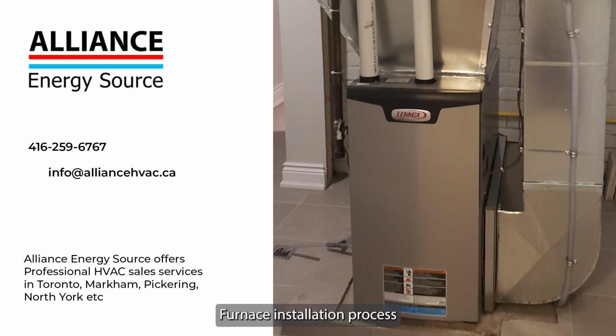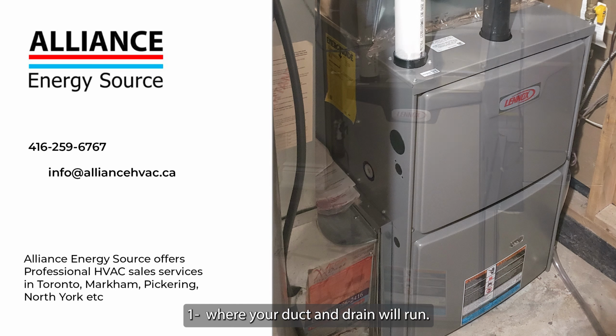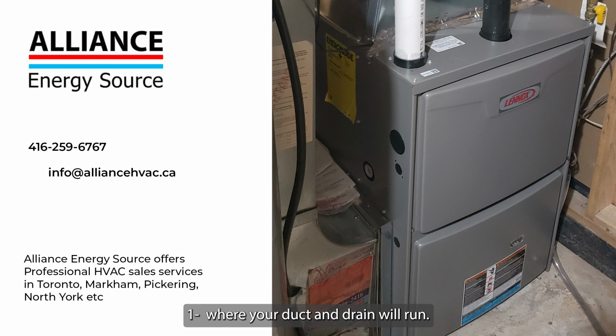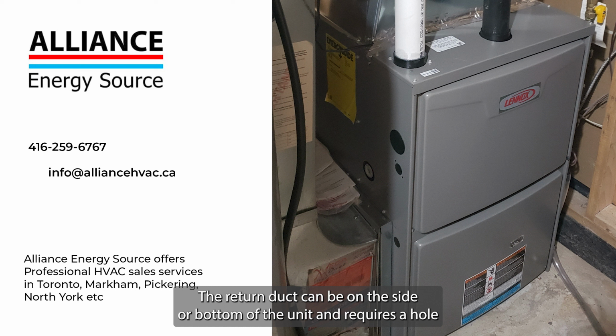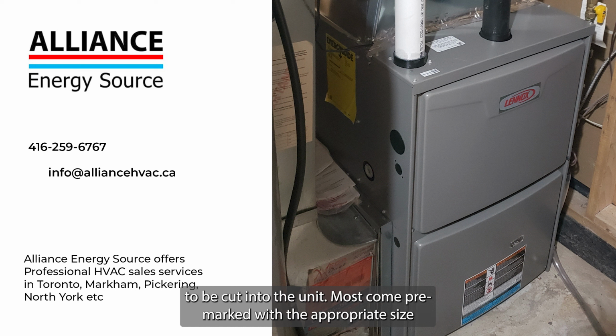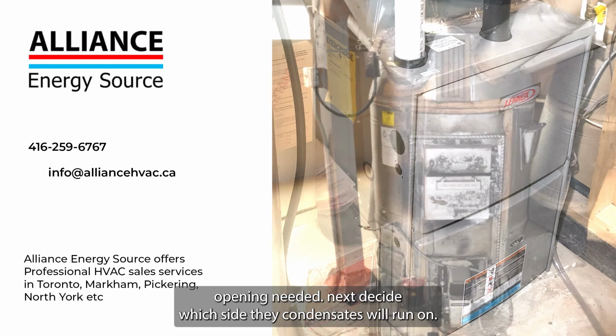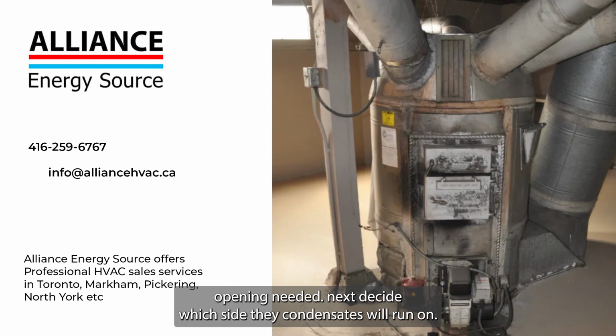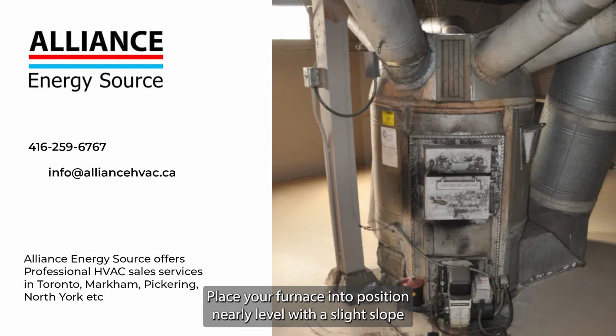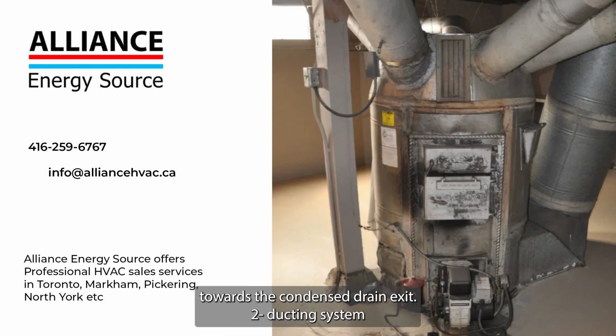Furnace installation process. 1. Where your duct and drain will run. The return duct can be on the side or bottom of the unit and requires a hole to be cut into the unit. Most come pre-marked with the appropriate size opening needed. Next, decide which side the condensate drain will run on. Place your furnace into position, nearly level with a slight slope towards the condensed drain exit.